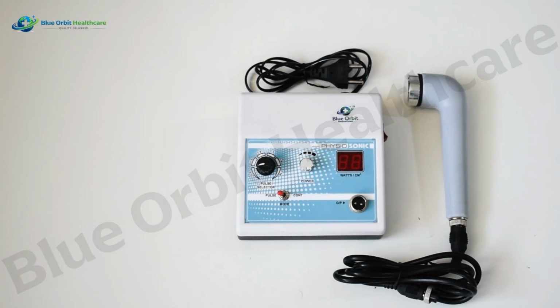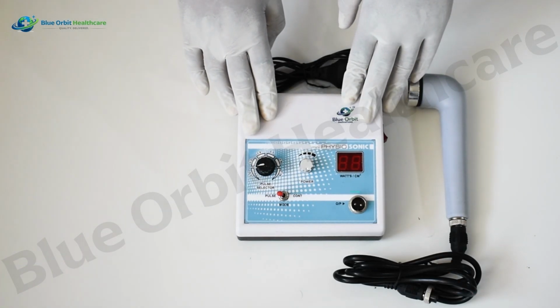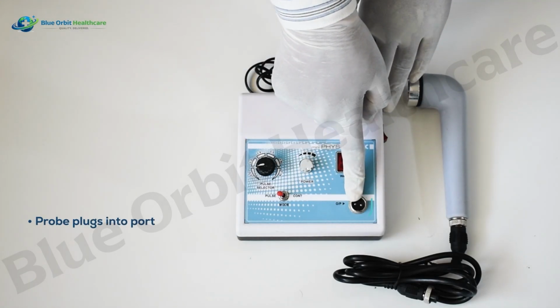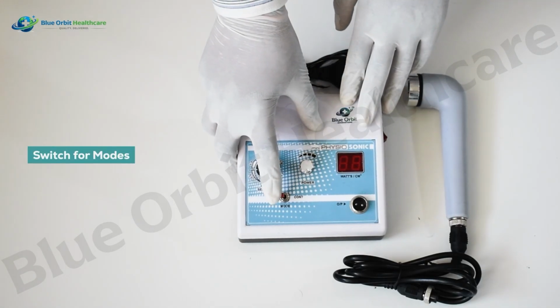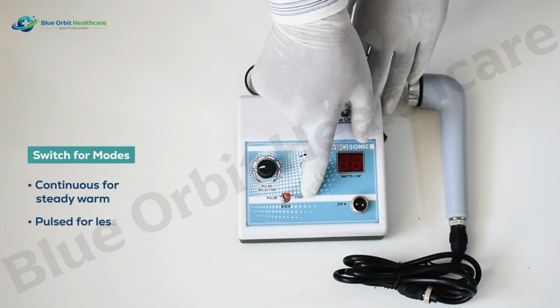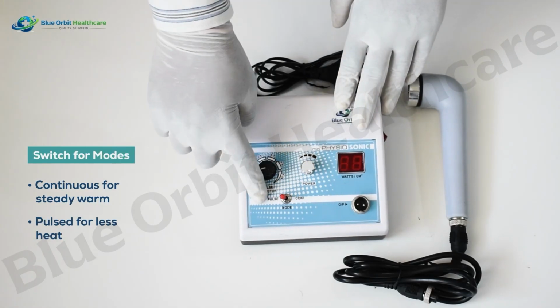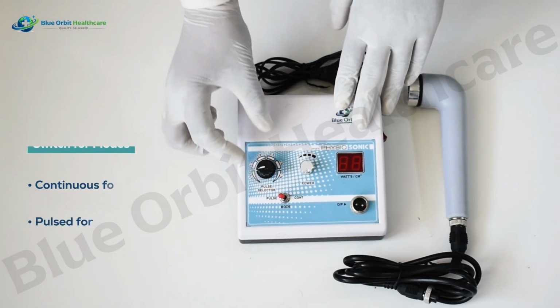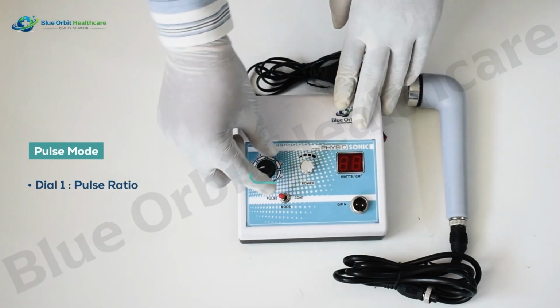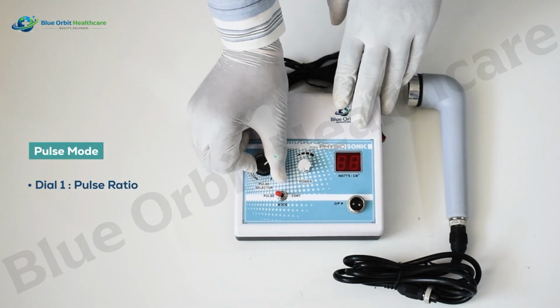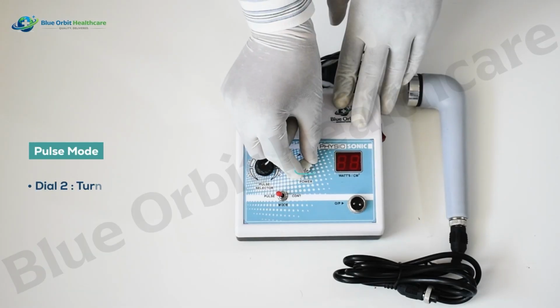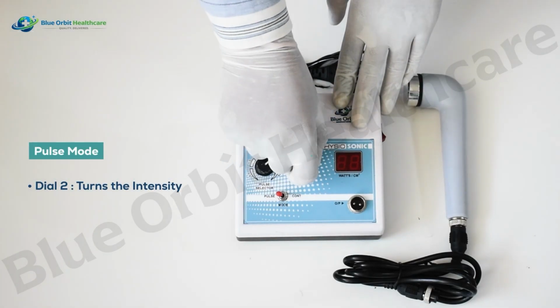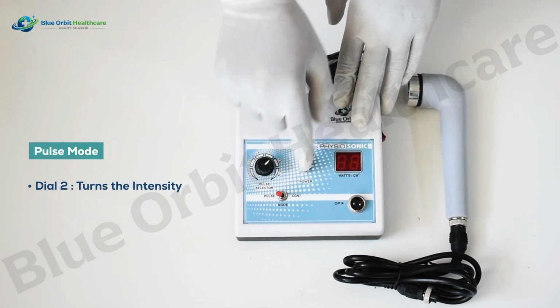This machine uses simple dials and a switch. The probe plugs into the port on the front. The switch sets the mode, continuous mode for steady warmth or pulsed mode for less heat. In pulsed mode, one dial sets how gentle the pulses are. The other dial turns the intensity up and the red screen shows it.